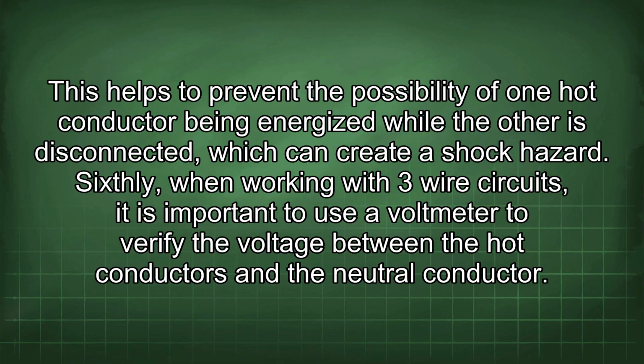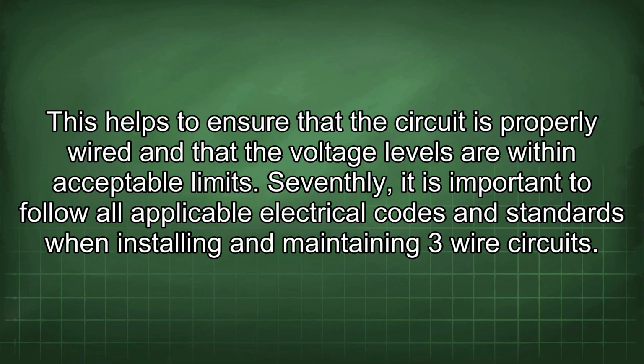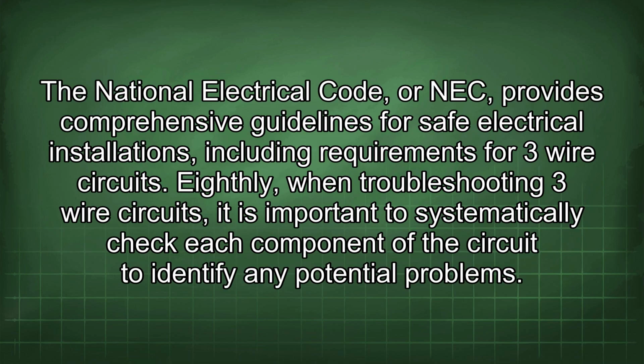Sixthly, when working with three-wire circuits, it is important to use a voltmeter to verify the voltage between the hot conductors and the neutral conductor. This helps to ensure that the circuit is properly wired and that the voltage levels are within acceptable limits. Seventhly, it is important to follow all applicable electrical codes and standards when installing and maintaining three-wire circuits. The National Electrical Code, or NEC, provides comprehensive guidelines for safe electrical installations, including requirements for three-wire circuits.